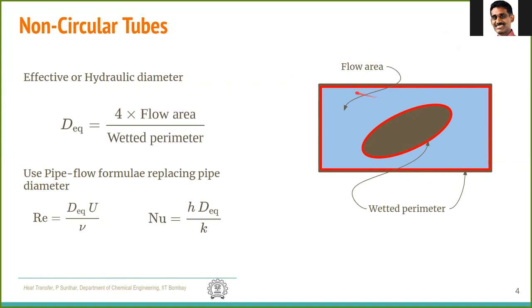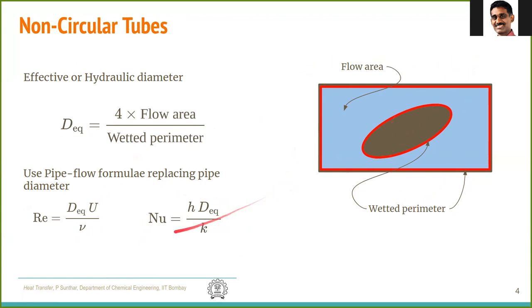We consider the wetted perimeter because it is where fluid and solid come into contact — that is where frictional and shear (wall stress) forces act. So 4 times flow area divided by wetted perimeter gives D_EQ. Once you determine D_EQ, you can use it to compute the Reynolds number for any arbitrary geometry. For heat transfer it is not perfectly accurate, but in the absence of specific correlations for these geometries, you can use D_EQ in place of the pipe diameter.